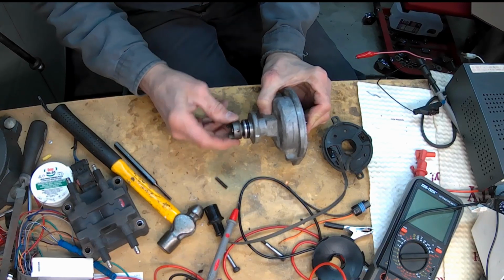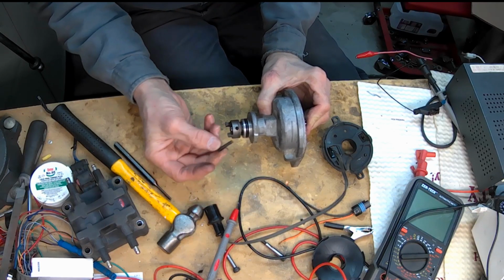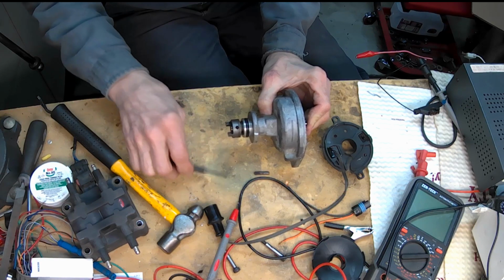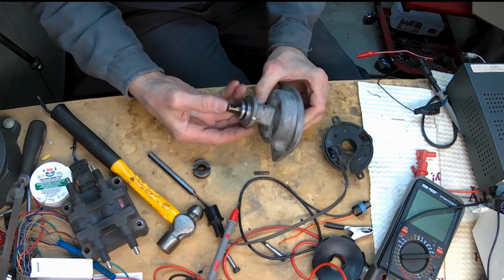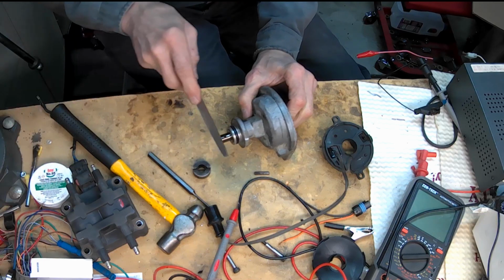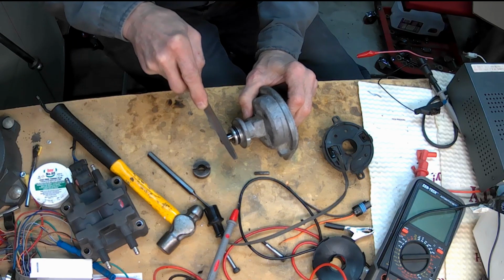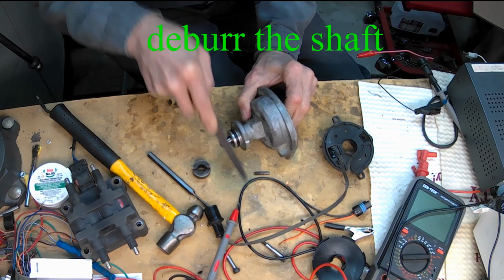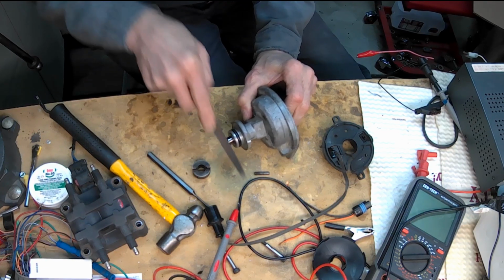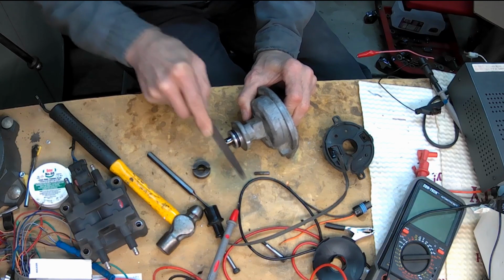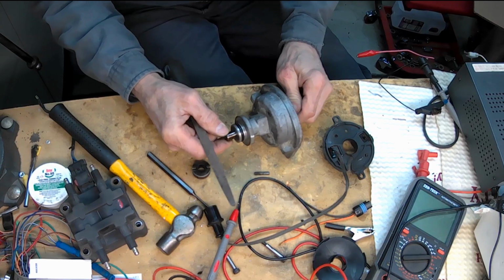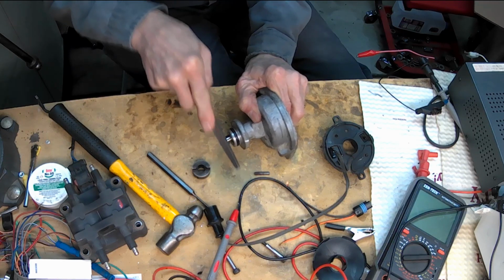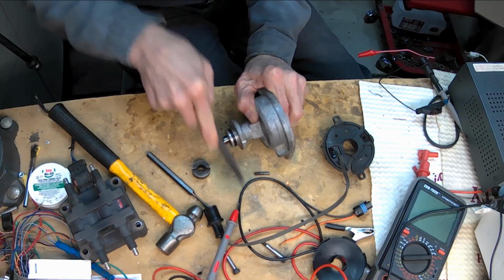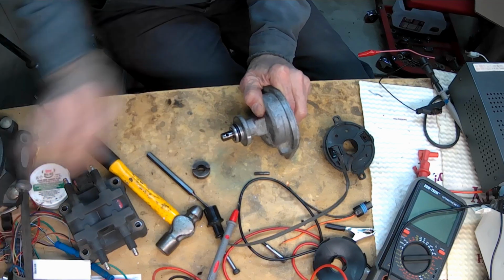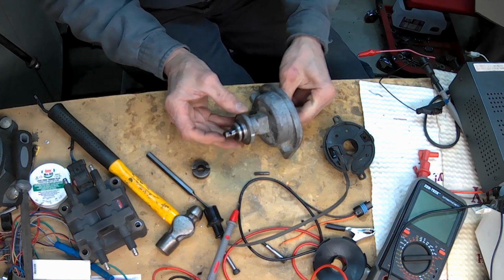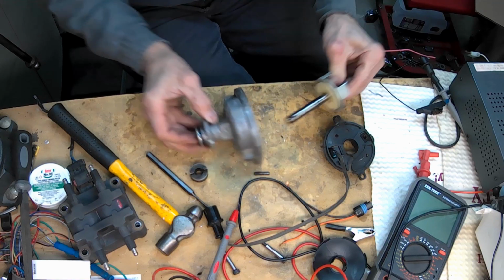So to remove the coupling at the end of the shaft, you drive out this drift pin with a punch, and then you want to remove the shaft, but first you'll have to take off a little bit of the edge that's formed there from the wear, just to make that smooth, and that pushes right through.